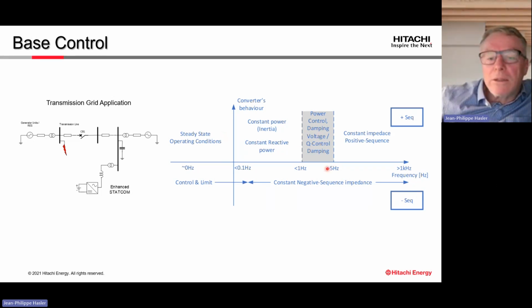And that finally defines the steady state operation. And in between these two types of control, between constant impedance and a stiff control, you will have some kind of gray zone, which is how the damping is done between these two different modes. For example, when you provide inertia, we know that when a machine provides inertia, the power increases, then we have an overshoot, and then a poorly damped oscillation. And what we are talking about in this scheme is how we define the damping when we have a rocof, for example, or how we define the damping when we have a step in the voltage control.